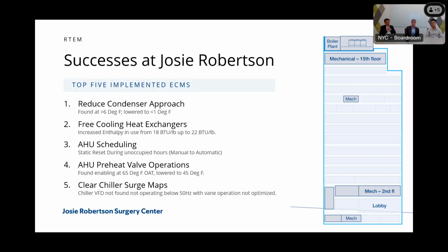Same thing goes to the AHU preheat valves, that we found them enabling at 65 degrees. The supply air temperature leaving those air handling units was still meeting set point, so it's not something that would flag any operators' concerns. So we adjusted those parameters.